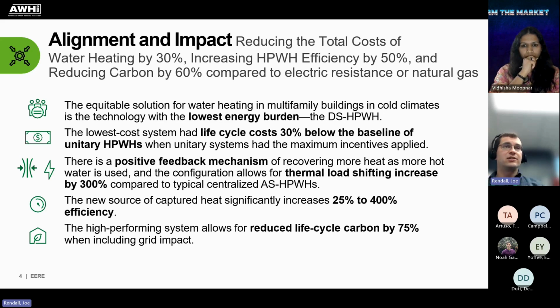Having this free energy source really increases your COP, especially in the dead middle of winter, is what we're modeling at this point. So if you're using electric resistance backups in the winter for your centralized air source heat pump water heater because the temperature went too low, you could still run your drain heat recovery system, your drain source heat pump water heater, at a high efficiency. That's how we get to the maximum of 400, in those really cold months and really cold, long, extended cold periods.